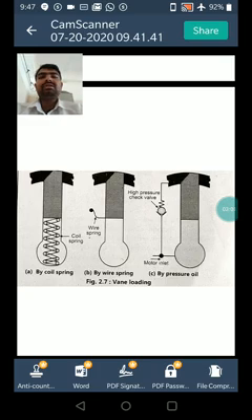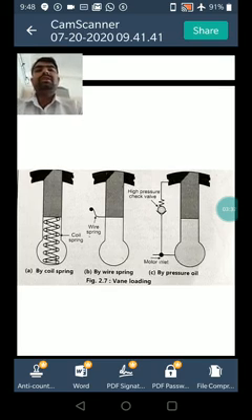That figure shows the vane loading. The spring loading can be of coil spring type or small wire spring. The wire spring is attached to a post and moves with the vane as it travels in and out of a slot. In the case of a vane loaded with hydraulic oil pressure, the fluid is allowed to enter the vane chamber only after the vane is fully extended and a positive seal is ensured.